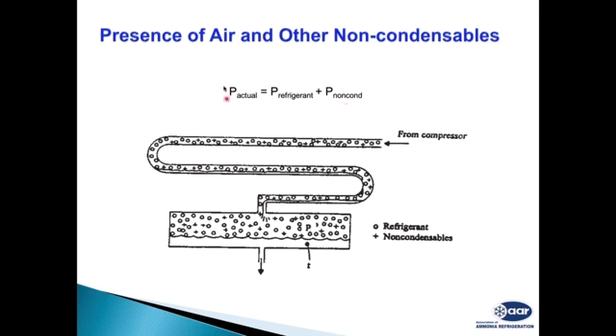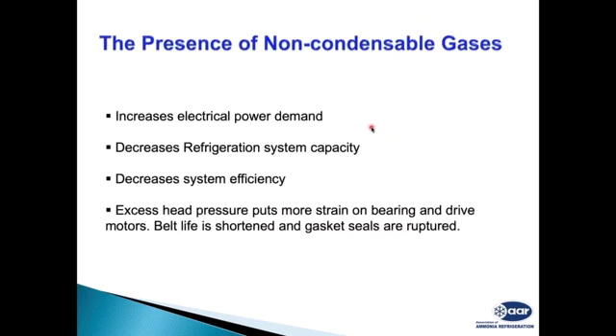For example, our gauge pressure is showing 14.5 and our liquid temperature is, say, 38, which means around 13.7, 13.8 kg per centimeter square pressure. So 14.5 and 13.8, a difference of 0.7 kg, is non-condensable gases. What happens with this air or non-condensable gases in our system is that it increases our electricity demand, it decreases our refrigeration capacity, and it affects the overall performance of the system.